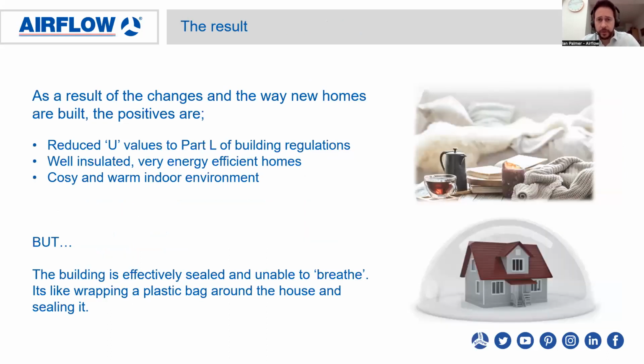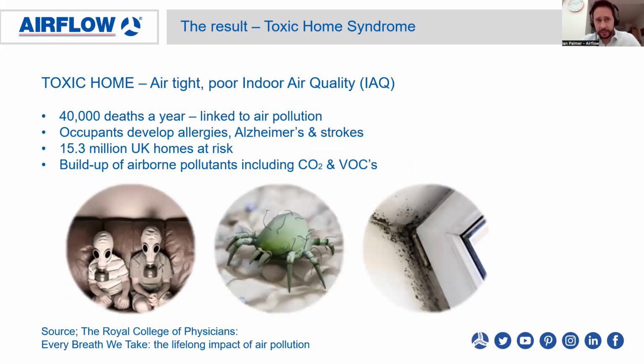So although the new homes will be nice and cozy, very warm, no drafts, the problem is it's almost like the house is in a sealed bubble, or plastic bag, as we reference here. And the problem with that is you've not naturally got any dilution of these airborne pollutants, because you've got very little airflow going through the homes. This is assuming you haven't got mechanical ventilation. And because of the air tightness, it leads to poor indoor air quality.